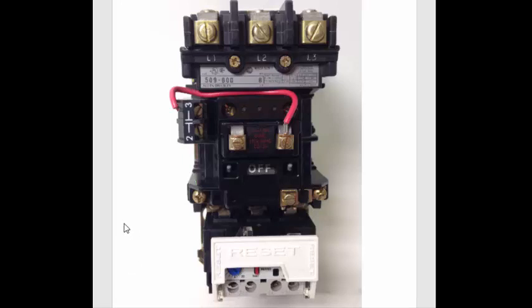the starter itself. So this is an Allen Bradley starter, and what we have here is the terminals where the three-phase power would come in. Typically we would use 208 volts three-phase going into the motor starter. What we have here is the coil. This starter acts like a relay, so when this coil is energized, three contacts close inside, one contact for each phase, which would then bring the power to the overload relay.